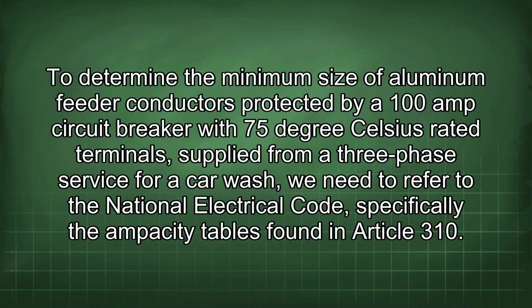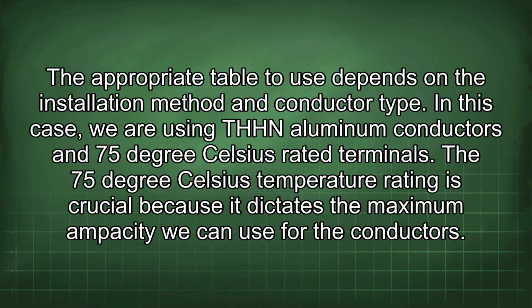To determine the minimum size of aluminum feeder conductors protected by a 100 amp circuit breaker with 75 degrees Celsius rated terminals supplied from a three-phase service for a car wash, we need to refer to the National Electrical Code, specifically the ampacity tables found in Article 310. The appropriate table to use depends on the installation method and conductor type.